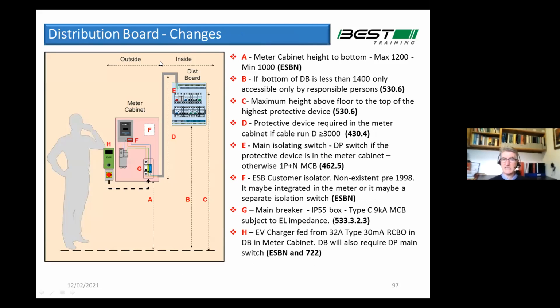And some other changes. This is a brand new slide, so it hasn't appeared in any of my presentations yet. Well, it did actually, yesterday. So it's again showing some other changes to do with consumer units. The height has changed. It's clarified now as 2150 to the top of the highest protective device, the top row of the protective devices. I think the previous one, it was 2250 to the top of the consumer unit. So it's 2150 to the top of things.